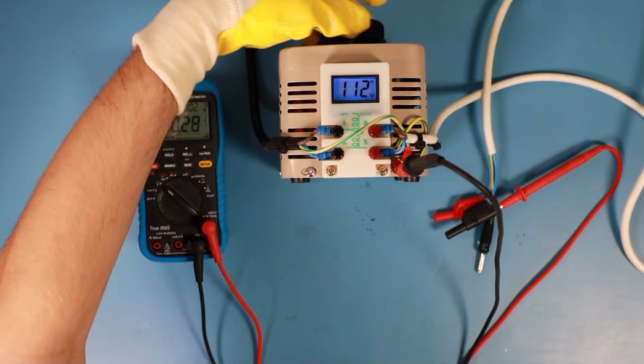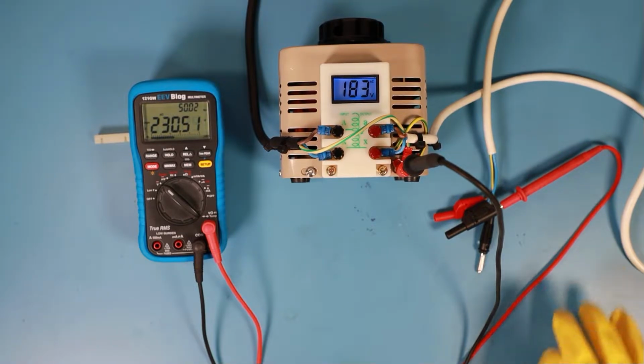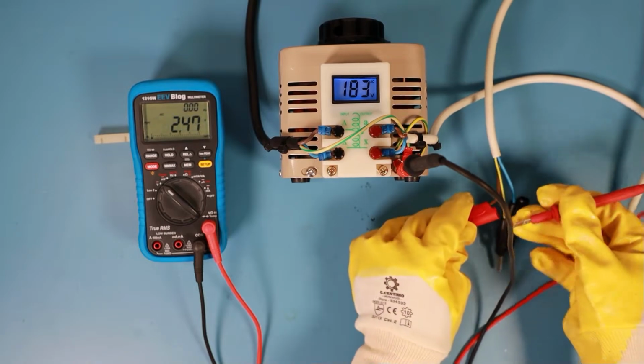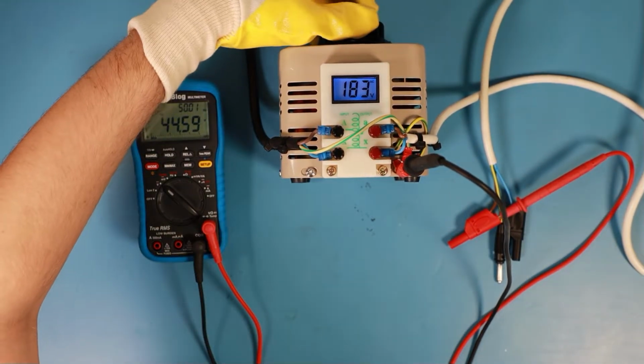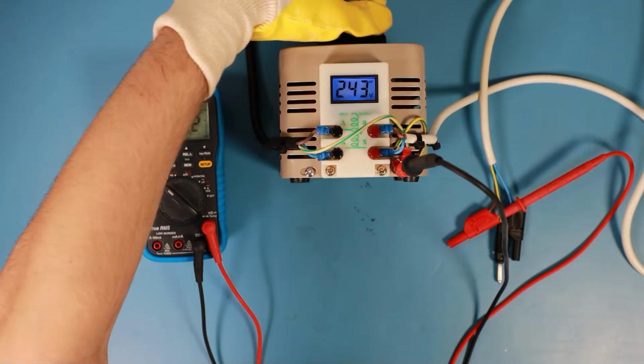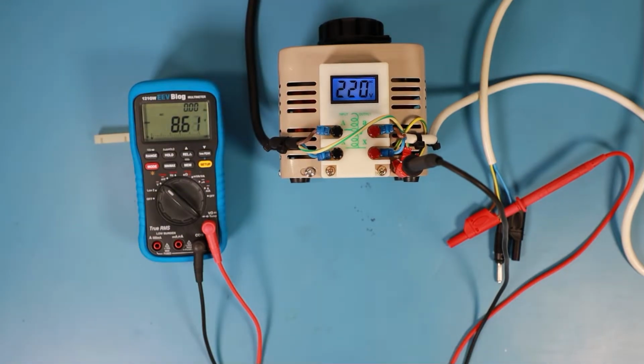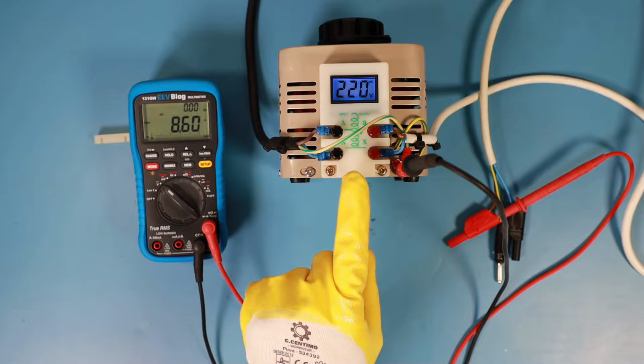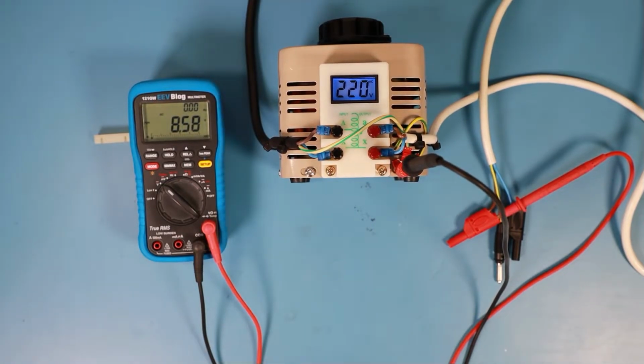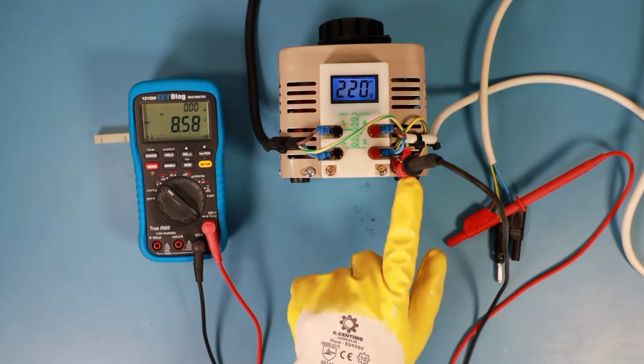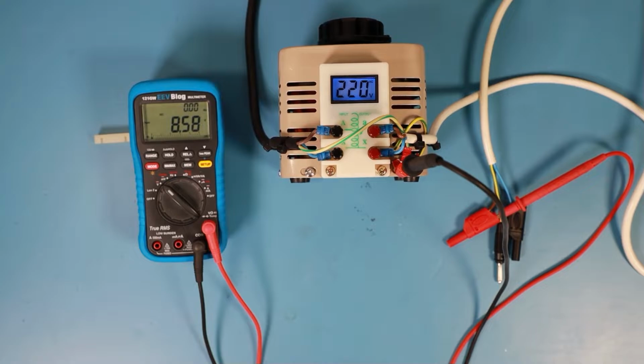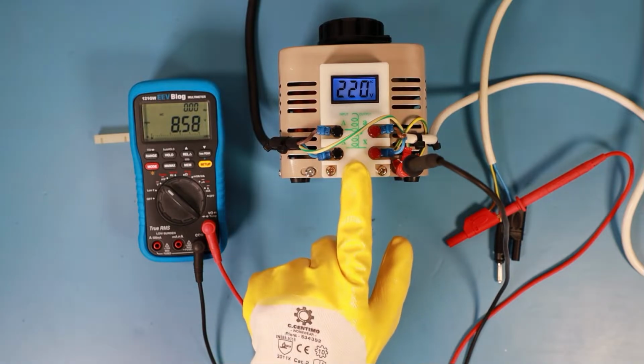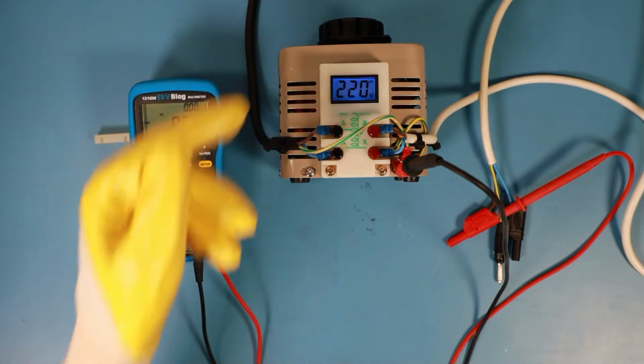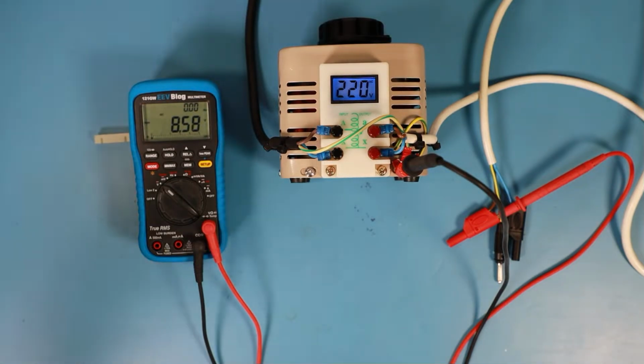Regardless of what I am selecting as output voltage. On the other hand, if I use the other connection, you can see that I kind of get a mirrored image. So I've selected a voltage that is close to the mains voltage, and when I measure between the live and the protective earth, I get close to 0 volts. This is happening because the transformer is actually working between the wrong connections. So it's letting phase through, and it's regulating the voltage on the neutral line. So I need to turn the plug around to get a correct picture.